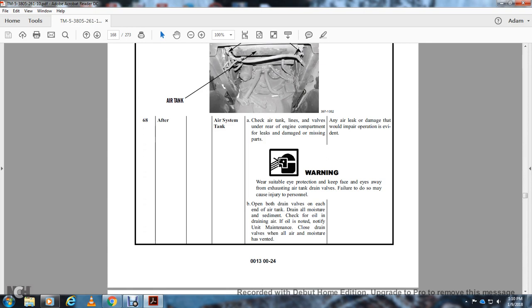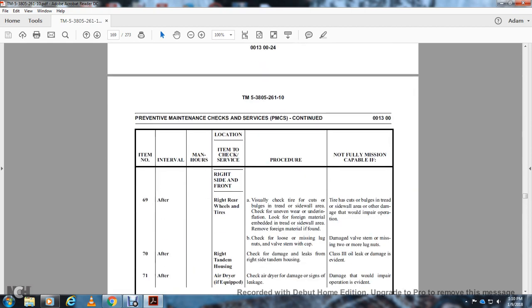Open both drain valves at each end of the air tank to drain all the moisture and sediment. Check for oil at the drain valve. If oil is noted, notify unit maintenance. Close drain valves when all air and moisture has been vented.